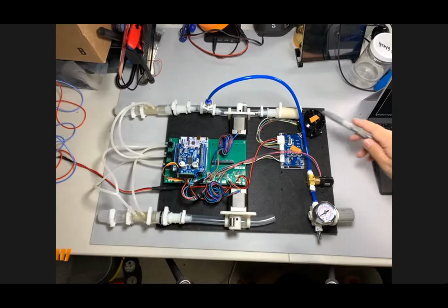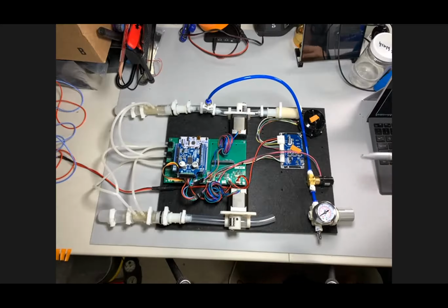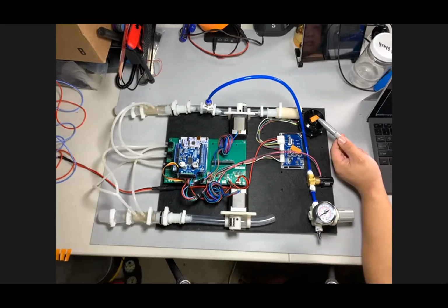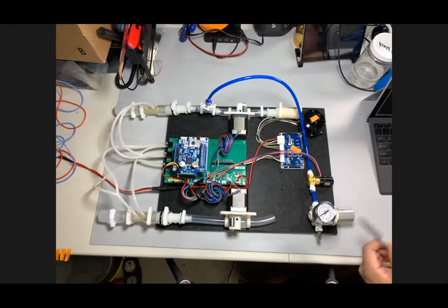So this is our ambient air source. The ventilator, being able to provide anything from ambient air to pure oxygen, needs to have two sources of input gas. We have an oxygen inlet here, and then we take ambient air from the environment. So this here is the oxygen input section. We have here a regulator that takes whatever unregulated oxygen tank input and brings it down to 10 psi, which is the operating pressure of the proportional solenoid.